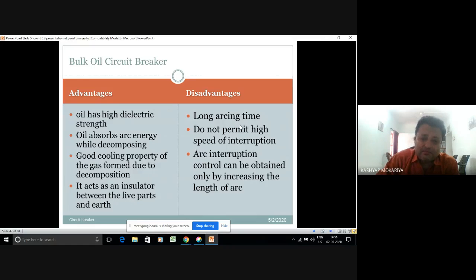Disadvantage: long arcing time. As compared to SF6 and VCB, you have a long arcing time here. The arc will sustain for quite a long time. It does not permit high speed of interruption. Now, if you are thinking of a recloser operation with an OCB, you will find that it will not permit a high speed of interruption. Arc interruption control can be obtained only by increasing the length of the arc. The length of the arc increases due to the turbulence action and the hydrogen gas occupying the space between the fixed contact and moving contact, which lengthens the arc path. This is different from the arc splitter reason used in an air circuit breaker in industry.